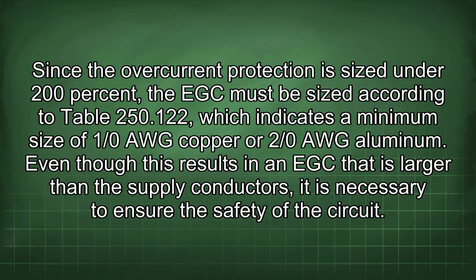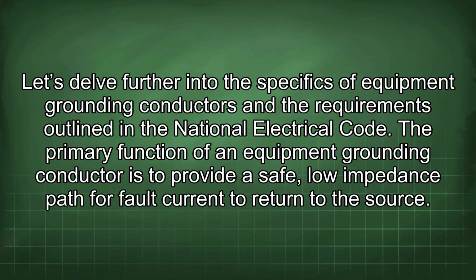Since the overcurrent protection is sized under 200%, the EGC must be sized according to Table 250.122, which indicates a minimum size of 1/0 AWG copper or 2/0 AWG aluminum. Even though this results in an EGC that is larger than the supply conductors, it is necessary to ensure the safety of the circuit.